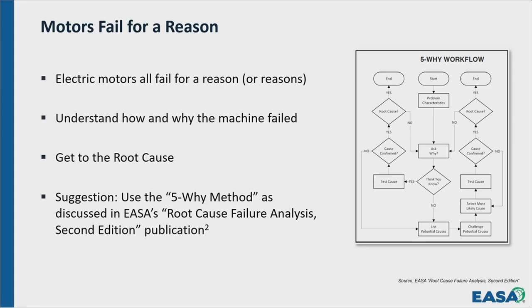There's been many studies and information about why motors fail, and EPRI and IEEE have put a lot of information out. Generally speaking, about half the failures end up being bearing failures on machines. Stators are about 16%, external sources 16%, unknown about 10%. We really don't know why it failed. And then we have rotor bar issues at about 5%. Again, these are general percentages.